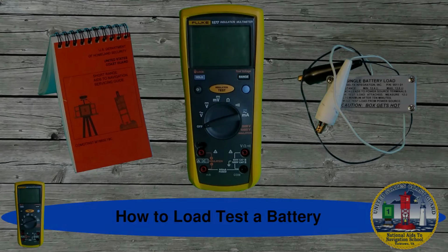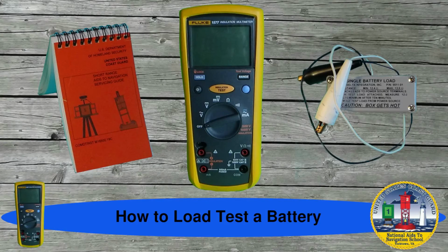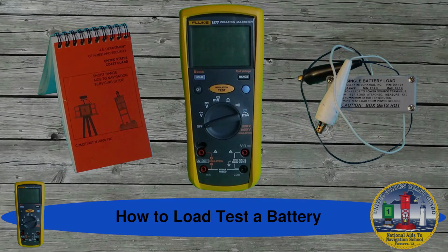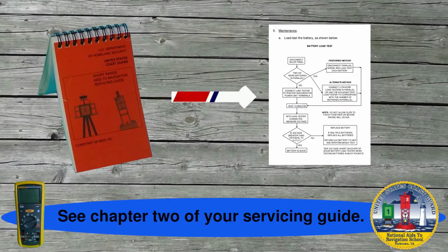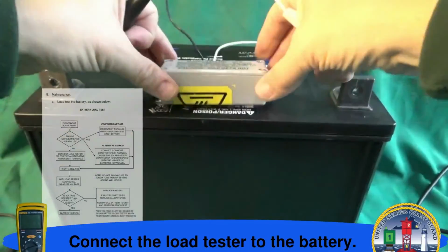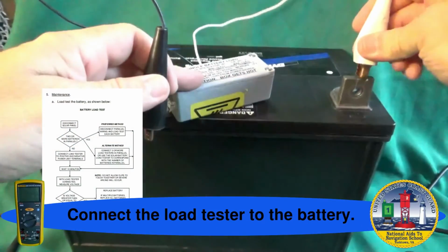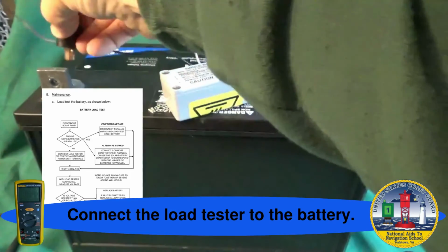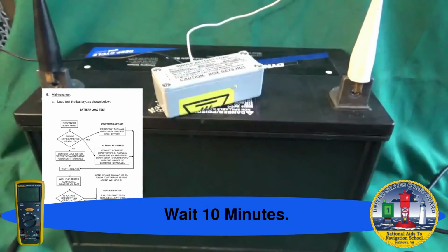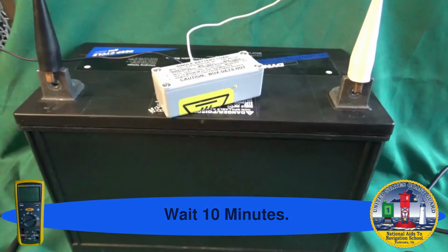With the battery disconnected from the aid and servicing cable, now is a good time to load test your battery. Chapter 2, Part 5 of your servicing guide describes this procedure. Connect a single battery load tester to the battery. Wait 10 minutes and check the voltage of the battery with the load tester connected.